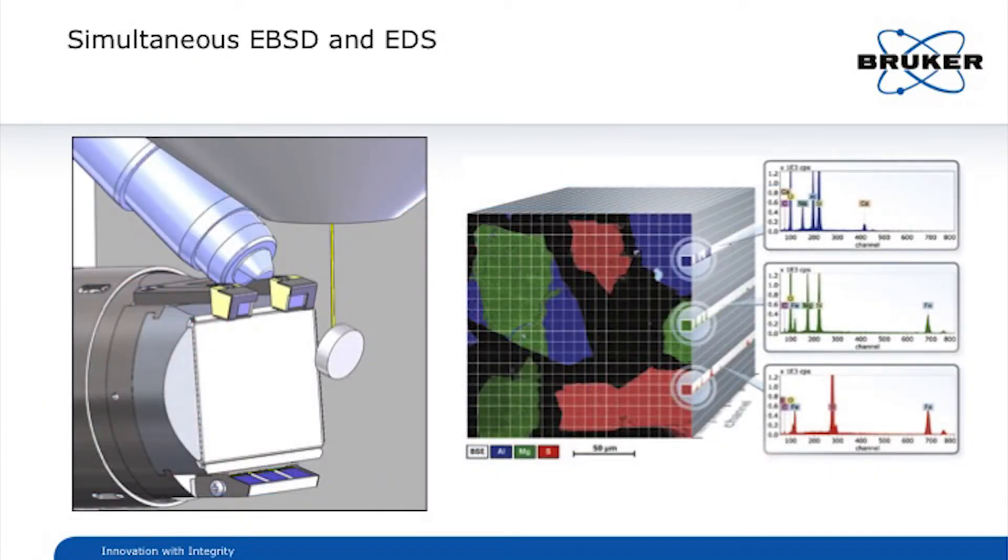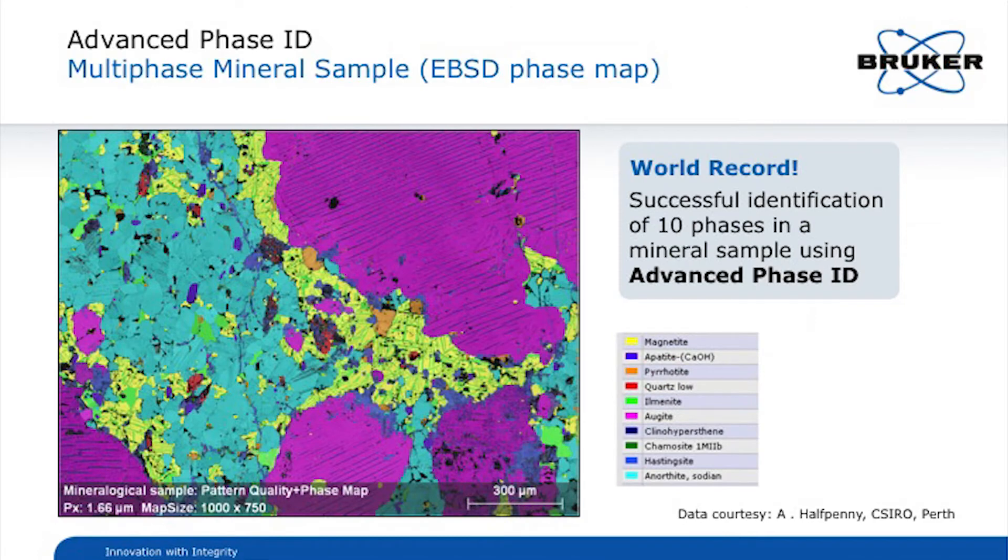Simultaneous EDS and EBSD mappings can be acquired with a speed of up to 930 patterns per second and the map data are saved as a position tagged hypermap database that includes both the EDS and EBSD results. The EDS spectra can be used for phase discrimination and for our unique advanced phase ID.